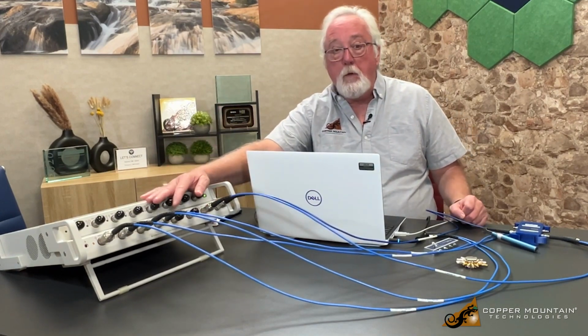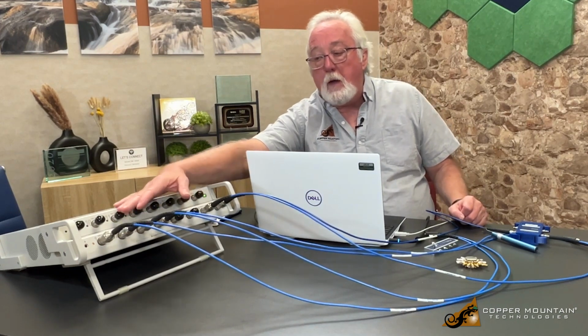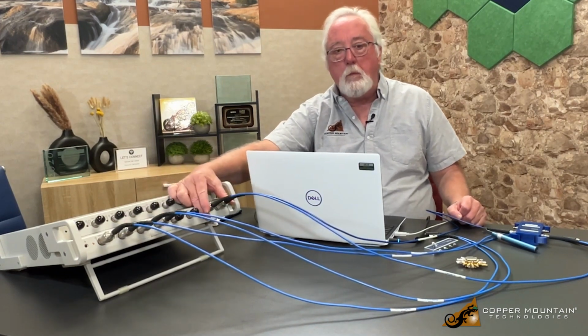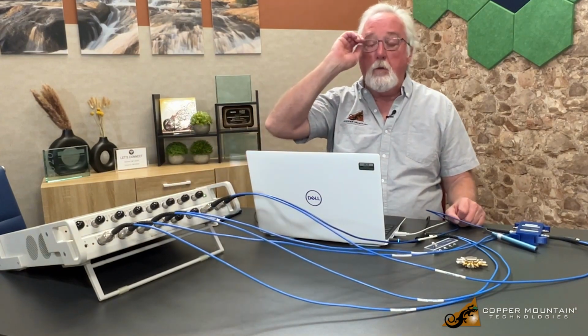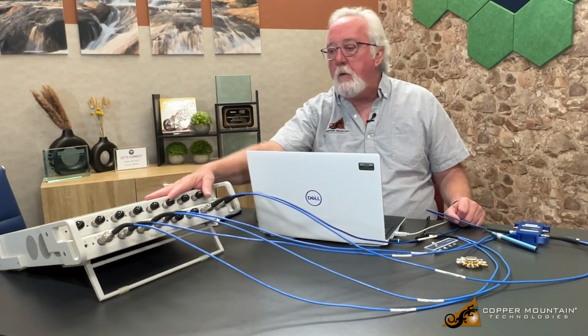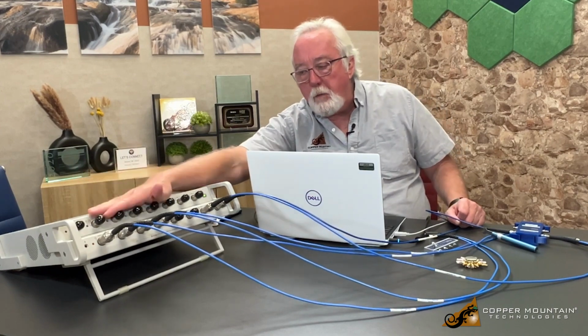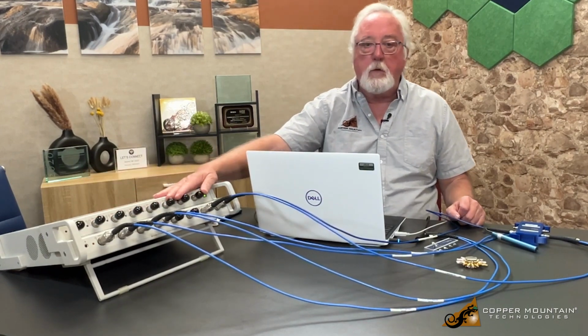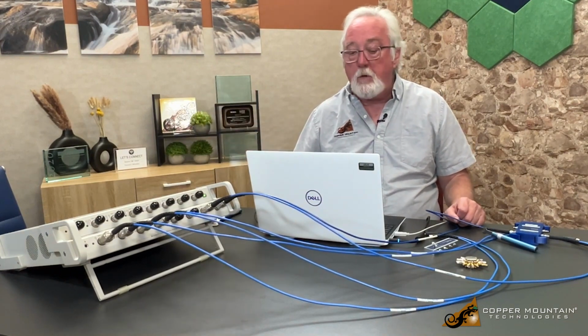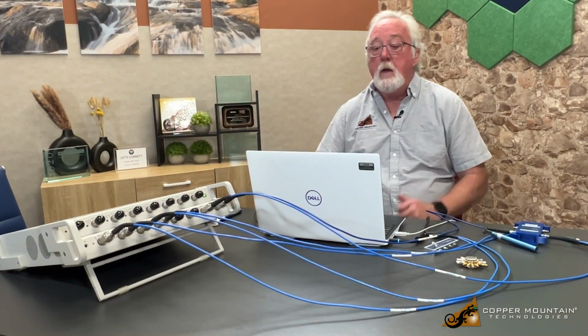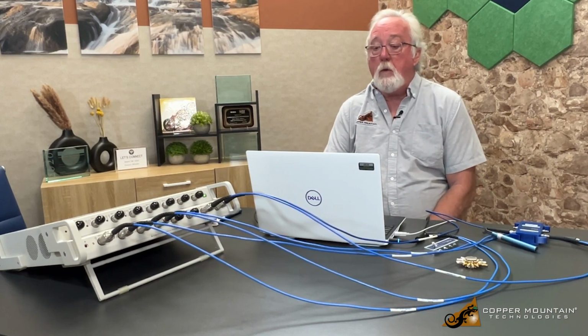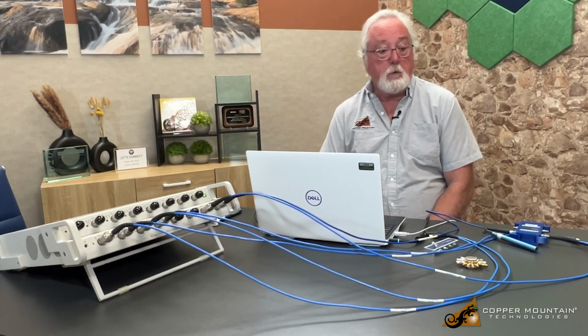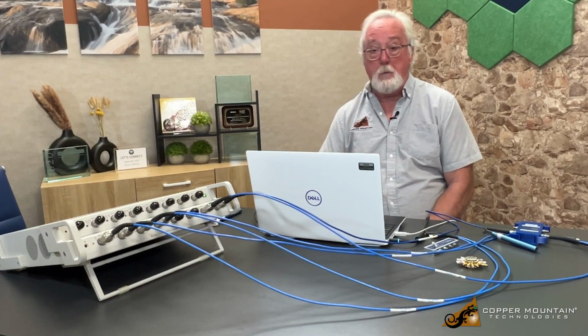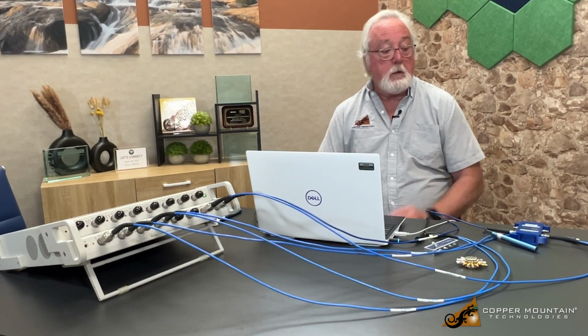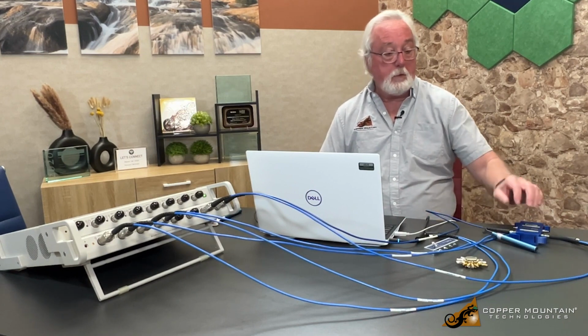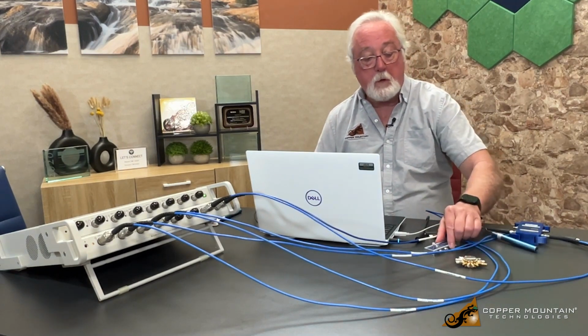Grouping the ports in this fashion allows you to do a separate 4-port and separate 2-port measurement with calibrations for each. So this is the most efficient way to do that. And I could add 3-port measurements and another couple of 2-port measurements for the other connectors. It allows you to do an awful lot simultaneously. The software is pretty easy to use. You could see that I went through this calibration quite quickly to do a fairly sophisticated measurement. We'll then use this measurement to measure the splitter and the filter in a subsequent video.